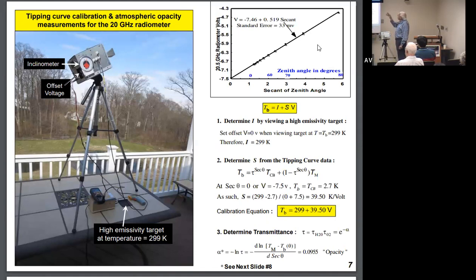Okay, now that curve has a slope, and that slope is what you're going to use for calibration, because you're doing linear calibration. Okay, first of all, you set the output from the radiometer to approximately 0 volts by changing the offset voltage with that little control. It's only done once. You get a temperature, you get a voltage, in this case, close to 0. And the intercept then is the temperature of the target, which is 299 Kelvin.